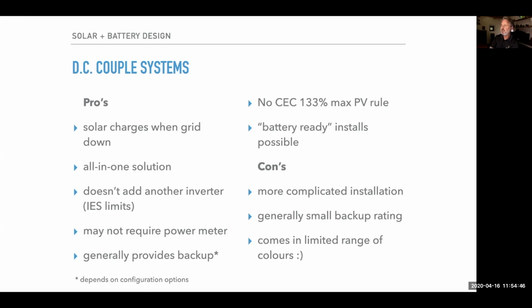On the con side, generally DC coupled systems are a little more complicated unless they're all in one package. They often have quite small backup ratings. When I say small, I'm talking like 2.3 kilowatts to about 5 kilowatts maximum. So they're designed for just essential loads, not running your whole house. And that last point's a bit of a joke.